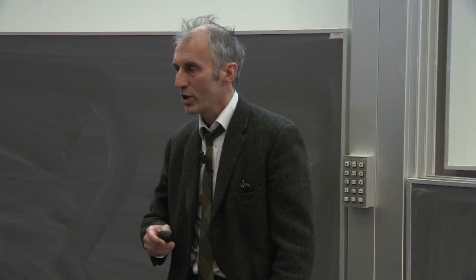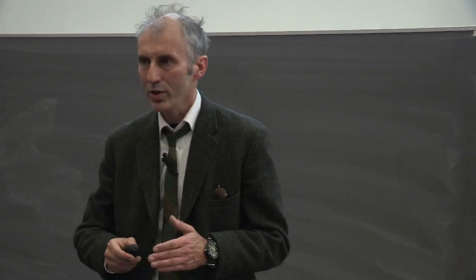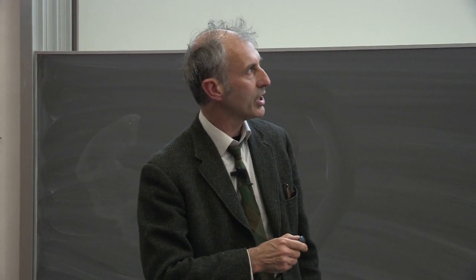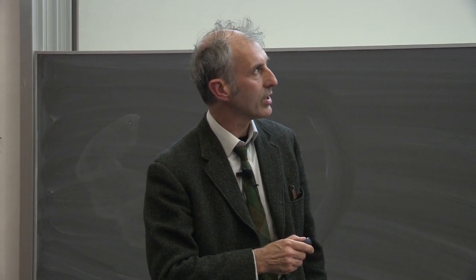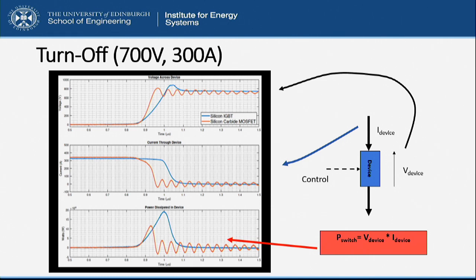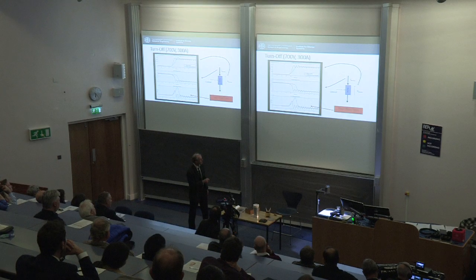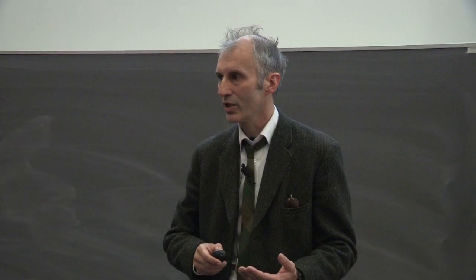This brings us to switching loss. Switching loss is important because it tells me how much energy I'm burning in that device every time I switch it. The product of current and volts gives me power. If I take those two together, I can see a small pulse of power dissipated in the silicon carbide device, with a bit of ringing, and a big pulse through the IGBT. You can see the losses are probably at least a factor of 5 down by going for that faster device.